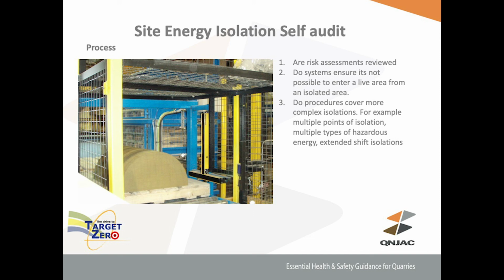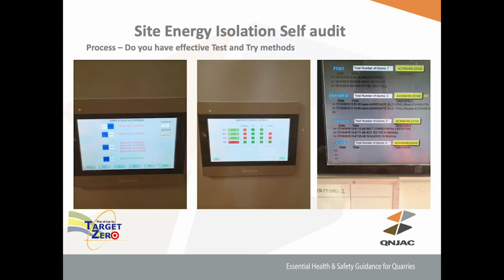The photograph on the left is about entering live areas from an isolated area. As you can see, that's at a precast factory, and those inverted T-shaped yellow pieces of equipment on the right are light curtains. Those light curtains should be used for preventing people going into a machine, and they're part of a safety control circuit. What those light curtains were being used for was to detect material and a pallet on that conveyor. You could make a mistake thinking that was a safety device, because that's what it's designed to do, but actually it wasn't being used as a safety device at the time. So you need to ensure that if you're using safety devices, you use them as safety devices and not as a product detection device.